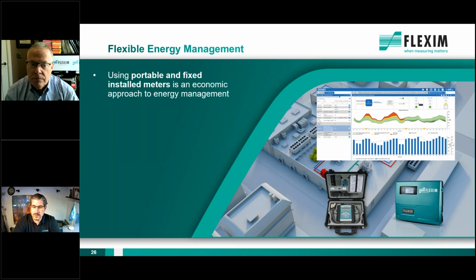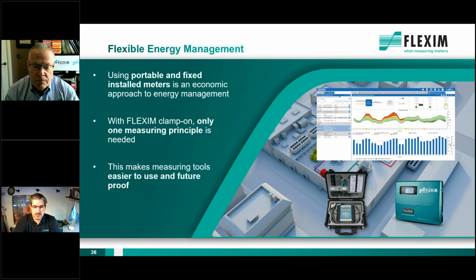Also, the ISO 50001, the standard for energy management systems, says you can use portable data from the field to feed your energy management system, to check your energy efficiency, and to get knowledge about your energy flows. So again, we have this one-for-all solution. Only one measuring principle is needed for all of these applications, and the combination of portable and fixed installed makes it easier to use and also future-proof, because, as I said, you will have some priority list where you want to start, and then you dig your way down to every spot in your estate. If you have this portable meter that can do it all, you will never run out of a tool that will help you. You have it at hand when you need it, so that you can go on and investigate further energy saving potentials.